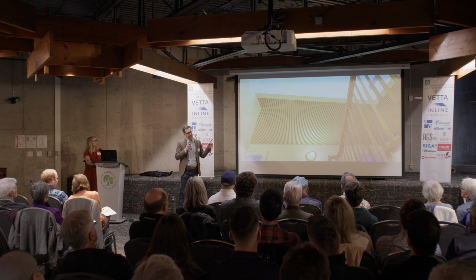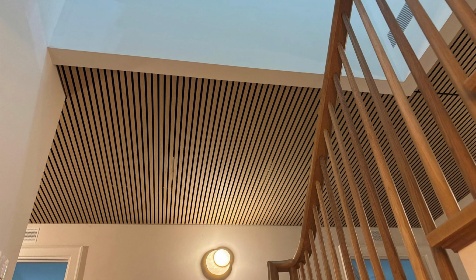So that is the second floor ceiling where we've got those 2 fan coils hidden. You absolutely need to think ahead to how you're going to service these units - you can't bury them. So that ceiling is all removable for maintenance over the life of the system.